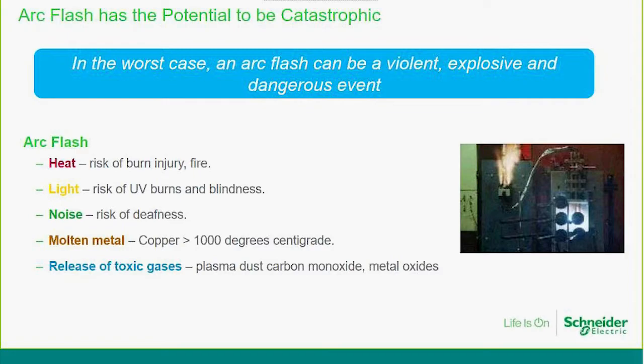You can have a partial discharge breakdown, you can have a circuit breaker clearing a fault whilst the door is open. This is the unknown. And really what arc flash tries to do is help you understand the risks associated with that. But if we look at the effects themselves, there's an awful lot of heat generated in a very short period of time. There's an awful lot of light, so very high frequency waveforms are created, and one of the clear aftermaths of such an arc flash incident is a tanning of the skin because of the levels of UV that are present during that condition. There's also a huge pressure wave created, so there's a risk of deafness.